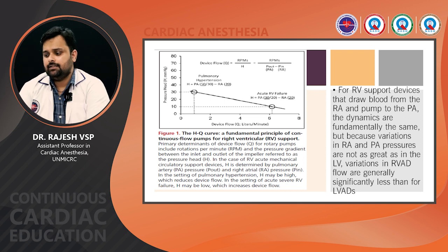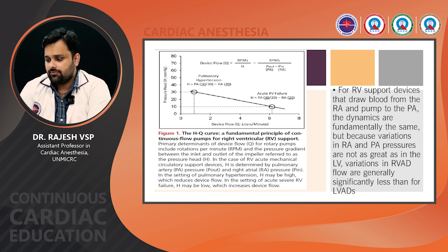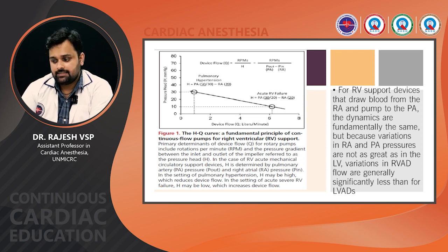For LVADs, the blood is drawn from the LV and pumped to the aorta. H is lowest during ventricular systole when LV pressure is greatest. Conversely, the pressure difference, that is H, is highest during ventricular diastole when LV pressure is at its lowest. Accordingly, because flow is inversely related to this pressure gradient, LVAD pump flow is maximum during systole and minimum during diastole. These dynamics are readily appreciated from the HQ curve of the pump.